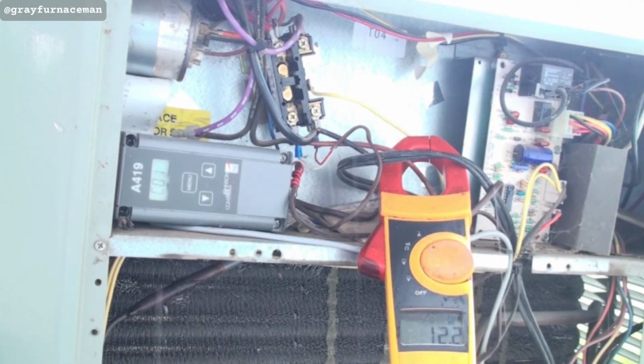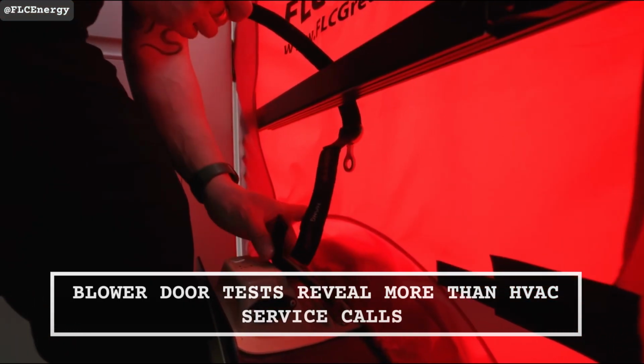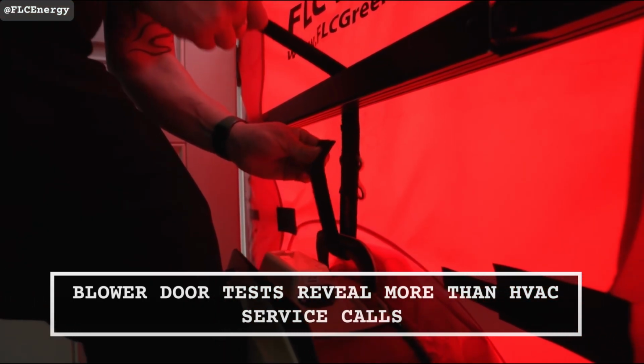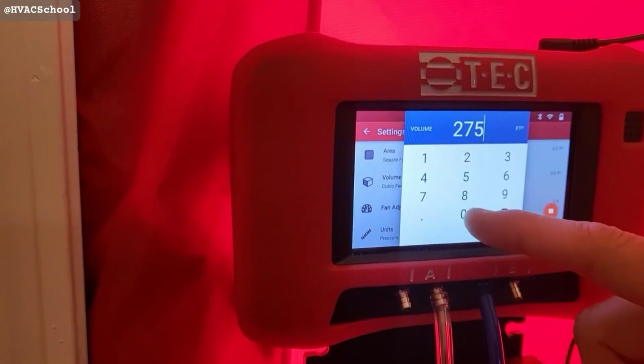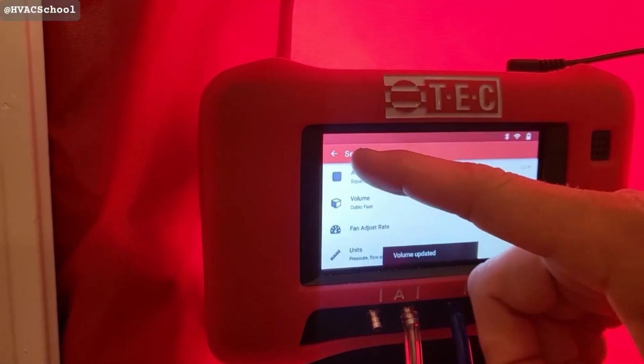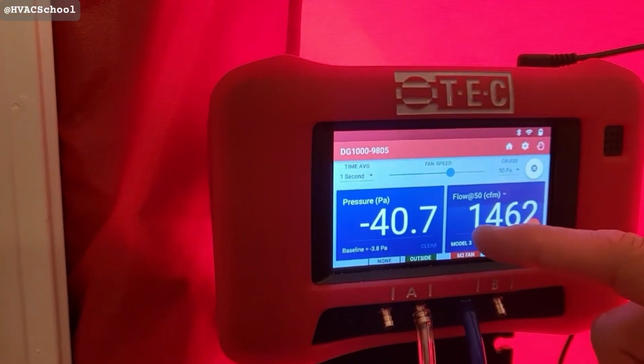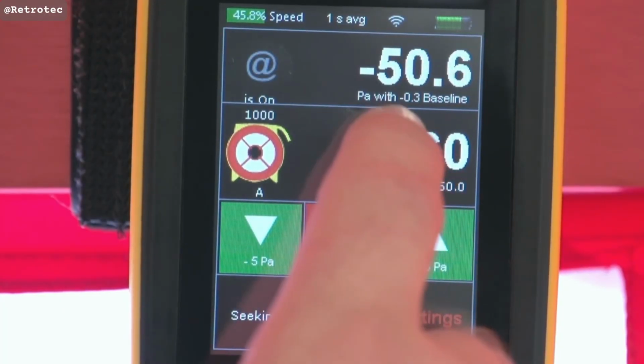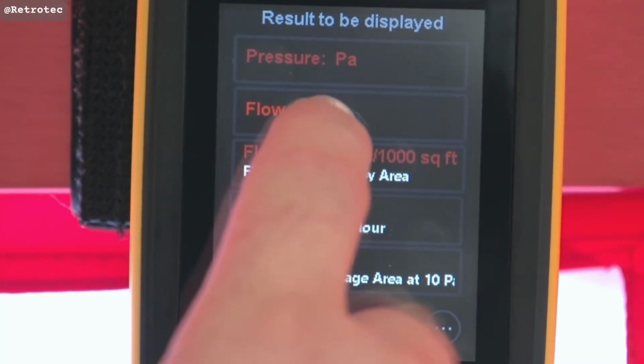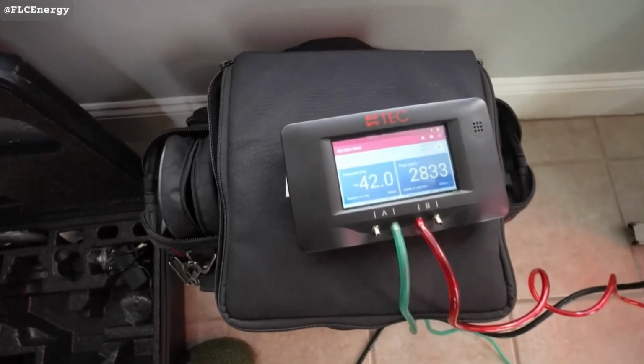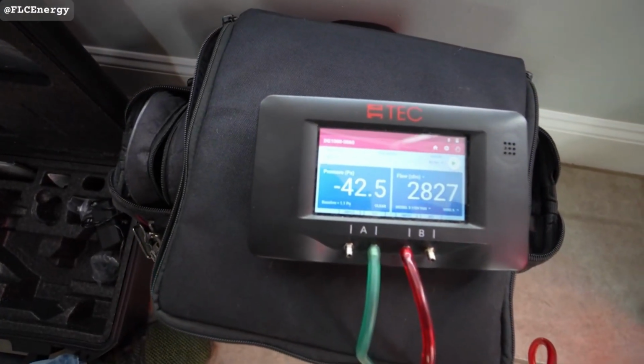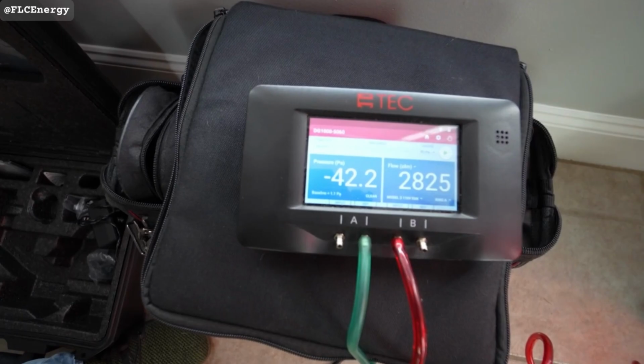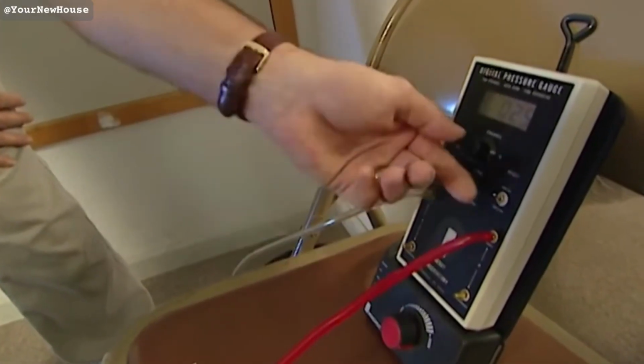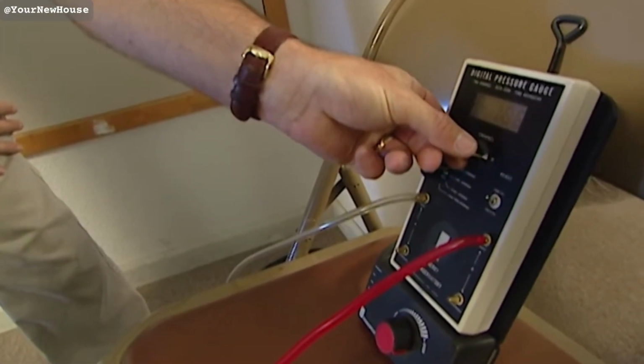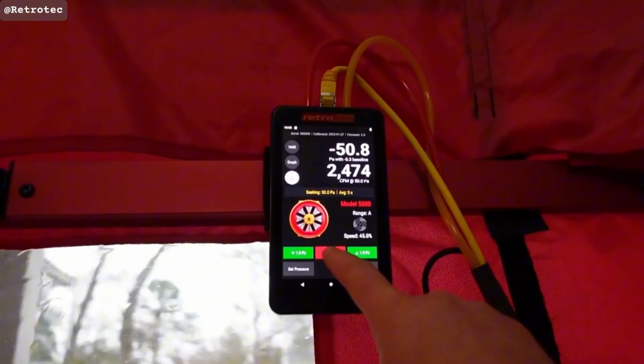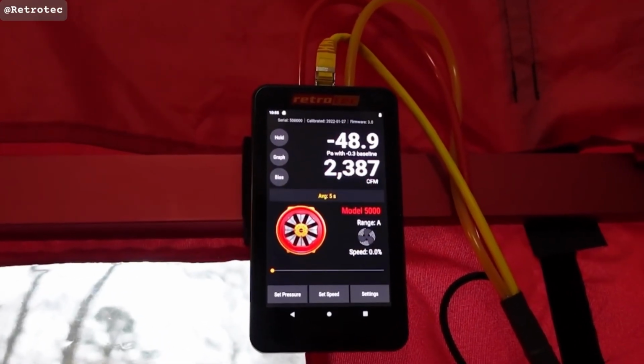Number 32. A residential blower door test run by a certified energy auditor costs $200 to $300 and tells you the exact air infiltration rate of your house, measured in air changes per hour. That number is more useful for diagnosing comfort and efficiency problems than any HVAC service call you'll ever pay for. A typical 1980s house leaks at 6 to 10 air changes per hour. A tight modern home runs 2 to 4. Knowing your number tells you whether to spend money on equipment upgrades or on envelope sealing first.